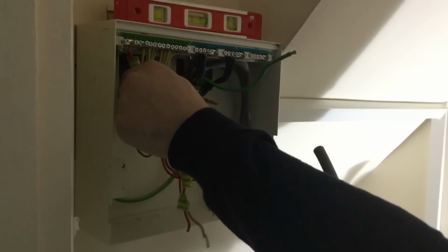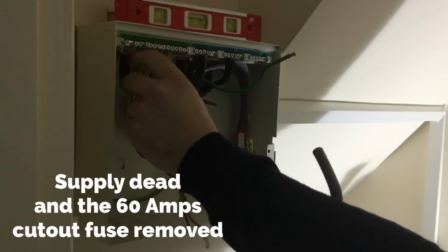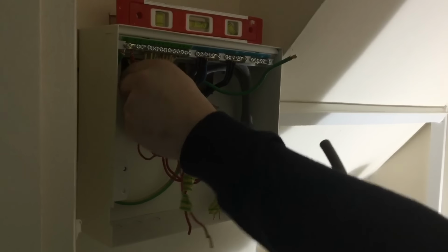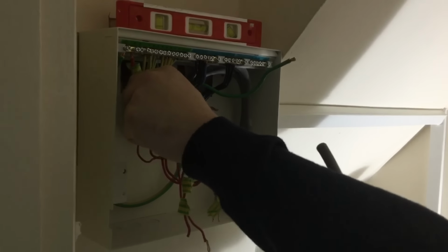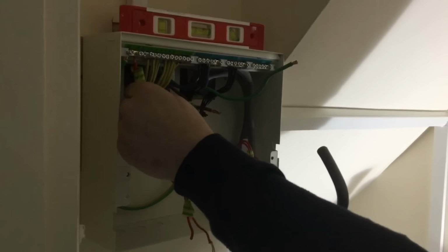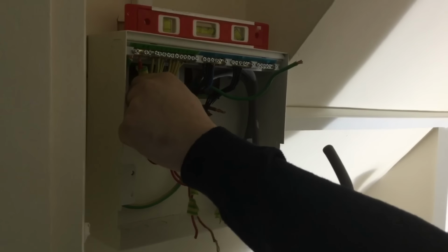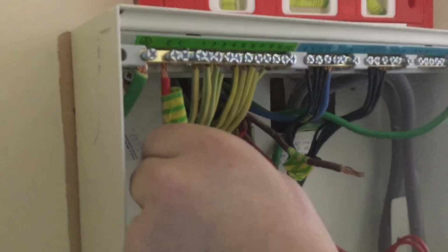So what test are we carrying out now then, Marcus? Now we're carrying out our first dead test, which is the continuity of the circuit protective conductors, including main and supplementary bonding. Okay, and which circuit are we going to start with? We're going to start with the cooker circuit. And you've linked that out to the earth bar, I see. So the line and the earth bar are connected together.